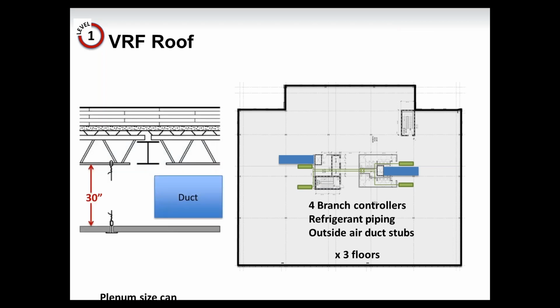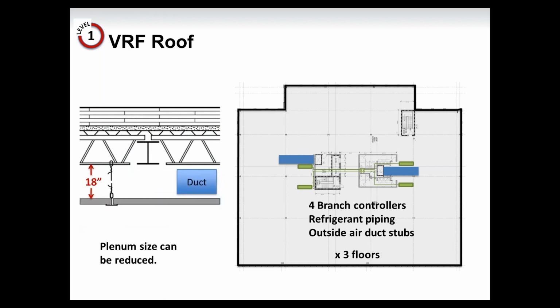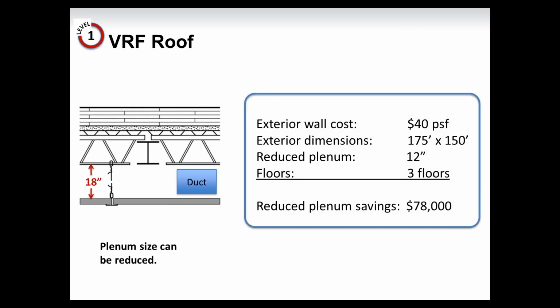Now this VRF system only requires ventilation of outdoor air, so a much smaller duct can be provided so the plenum size can be reduced. Now you'll only need an 18-inch plenum instead of a 30-inch plenum as per the rooftop design, and that equates to some owner savings. The exterior wall cost is approximately $40 a square foot. If you do the math with the exterior dimensions, 175 by 150, reducing at 12 inches per floor over 3 floors, provides a reduced plenum savings of $78,000, and that will show up in the other costs on this next screen.